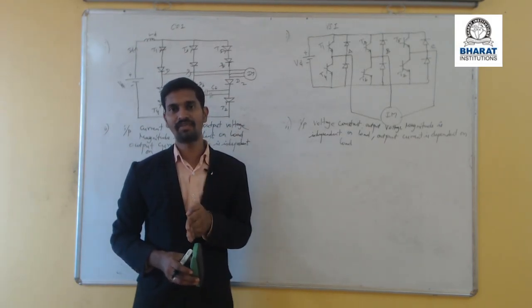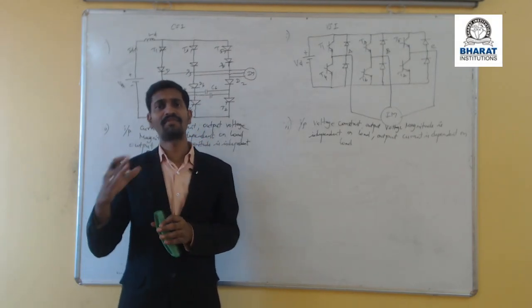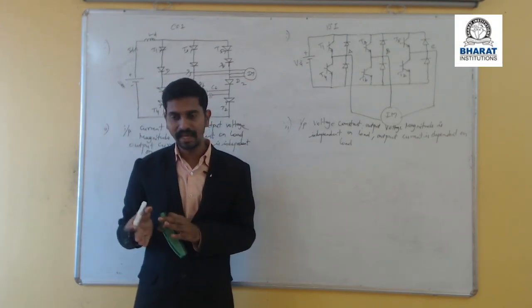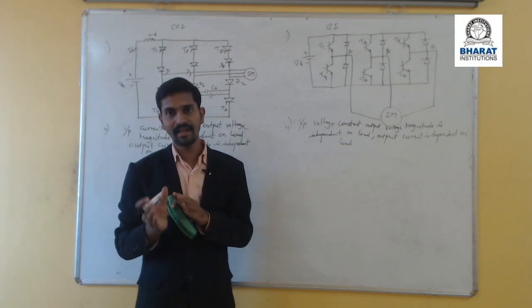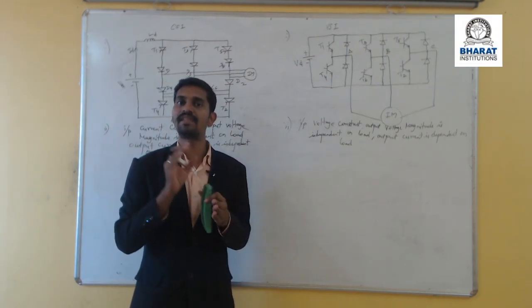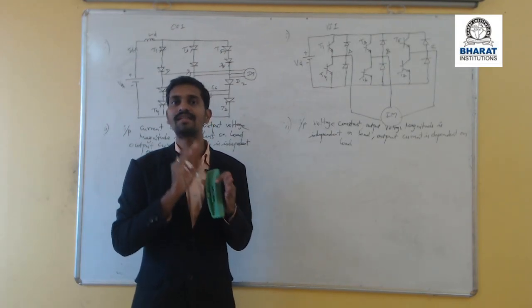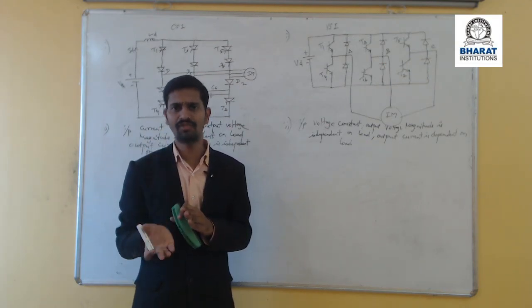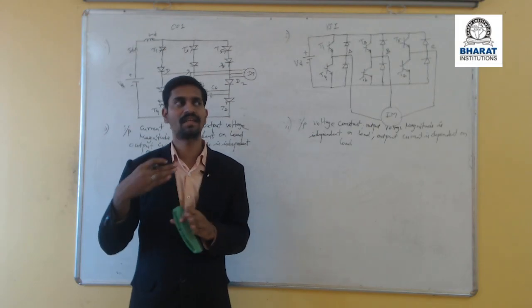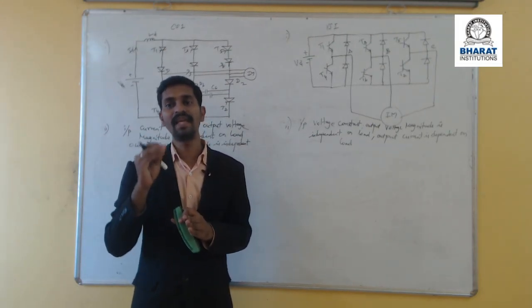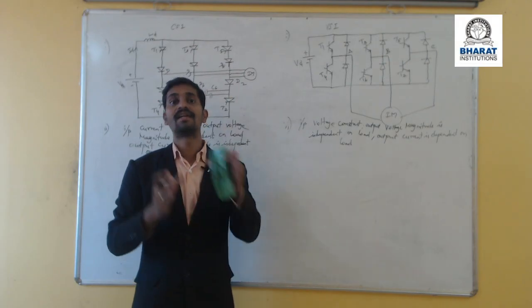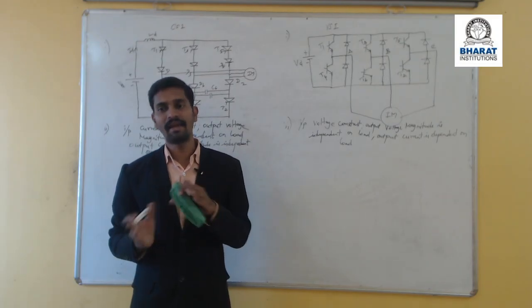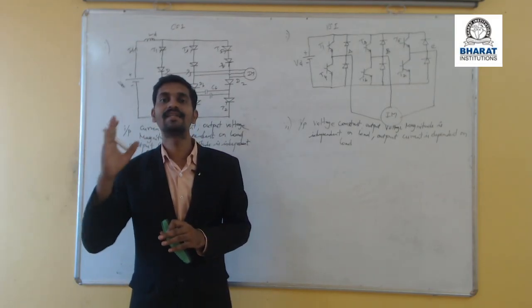Based on the reference frequency, the induction motor speed will be varied. We sense the induction motor speed, and based on the speed error, the reference frequency is set with the help of controllers. Based on the reference frequency, the appropriate firing angles of the thyristors or switching devices in VSI, CSI, or cycloconverters are given, and based on that firing angle, the motor runs at variable frequency and variable stator voltage.